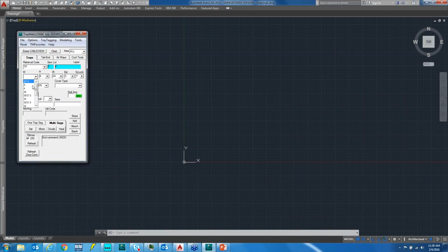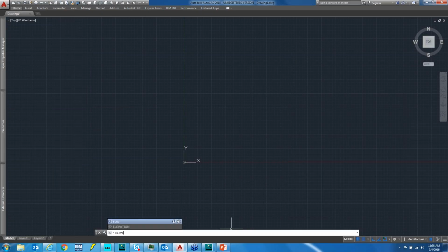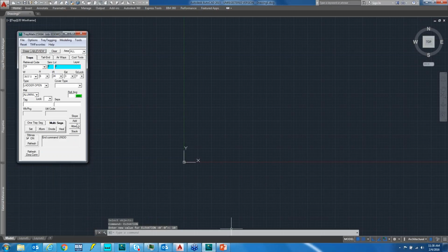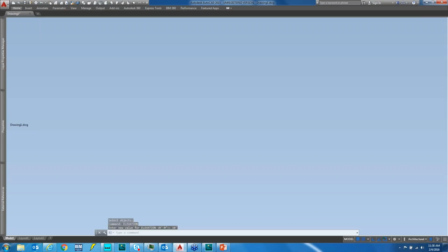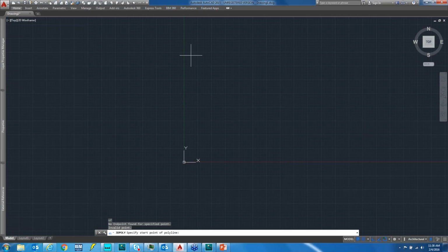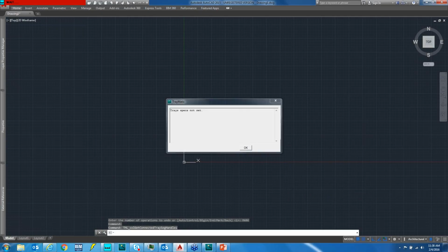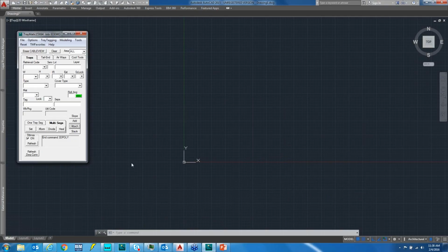So with all that said, let's pick a width. We're going to start with a 36-inch tray, and in order to add the tray, first we'll set our AutoCAD elevation to, let's say, 10 feet. Then we'll start modeling tray. You pick attach, and then it's very simple to just point and shoot. Put your tray in where you want it to go, and the tray spec is not set.